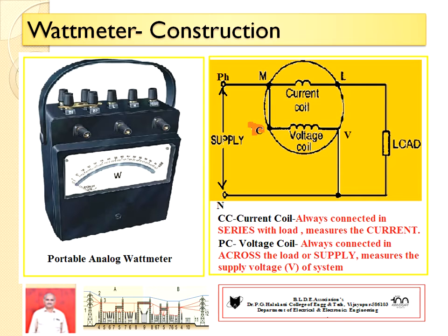In similar fashion, another coil is referred to as the voltage coil. In the diagram, between C and V terminals, the voltage coil exists, also called the pressure coil or potential coil. From M to C the connection is shorted, then V is given to neutral. So it is always connected in parallel to the supply which has to be measured, or across the load. The amount of current flowing through this voltage coil is directly proportional to the applied voltage of the given electrical system.